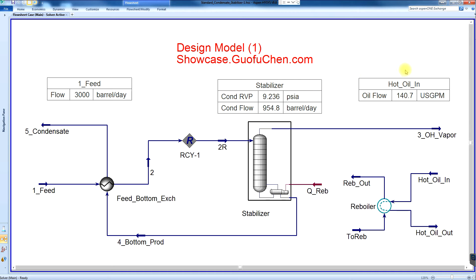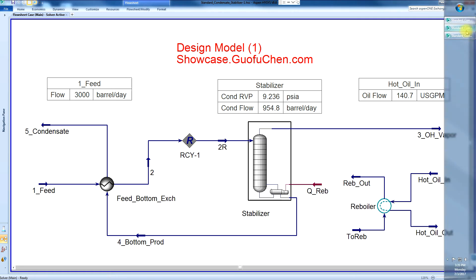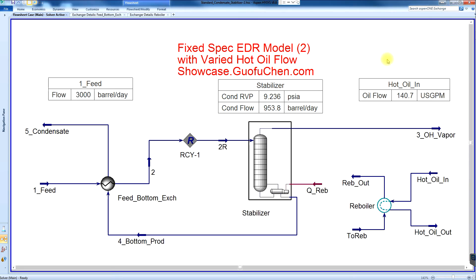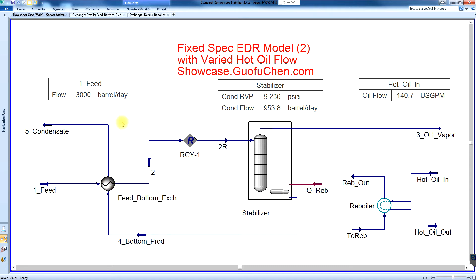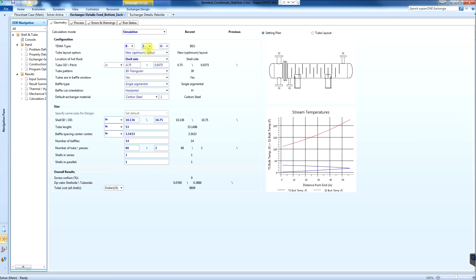The next step towards standardization is to integrate heat exchanger design into simulation software like Aspen HySys. In this second model, the heat exchanger geometries are input into the simulation. As you can see, the feed exchanger is a BU type with a shell diameter of about 10 inches and a tube length of 53 inches.